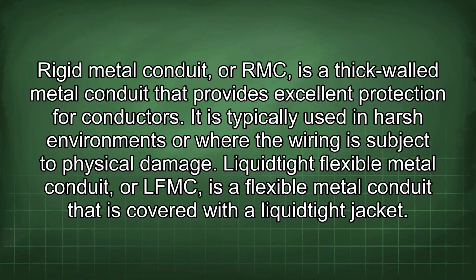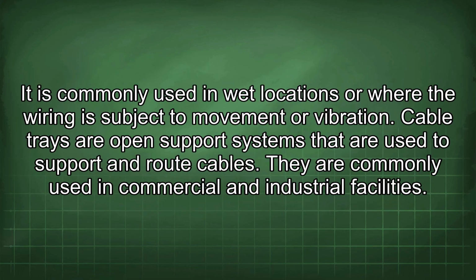Rigid metal conduit, or RMC, is a thick-walled metal conduit that provides excellent protection for conductors. It is typically used in harsh environments or where the wiring is subject to physical damage. Liquidtight flexible metal conduit, or LFMC, is a flexible metal conduit that is covered with a liquidtight jacket. It is commonly used in wet locations or where the wiring is subject to movement or vibration.